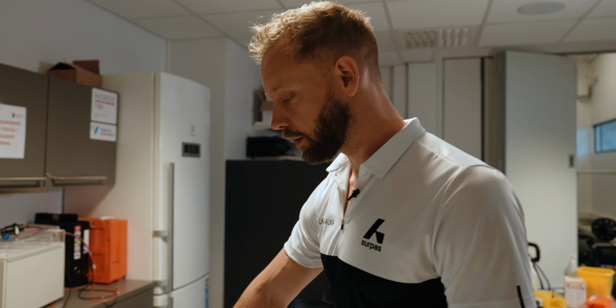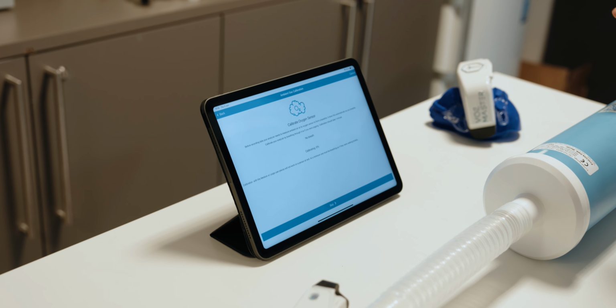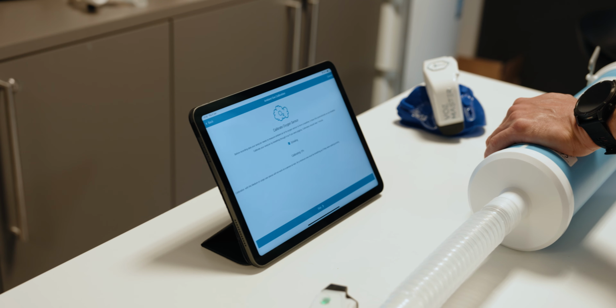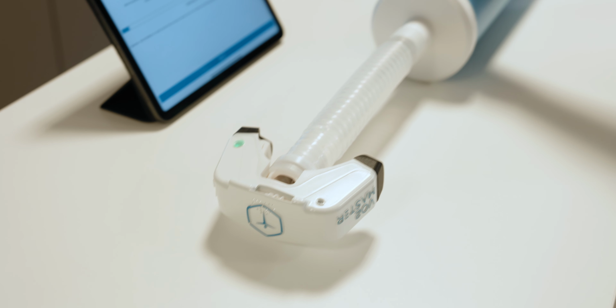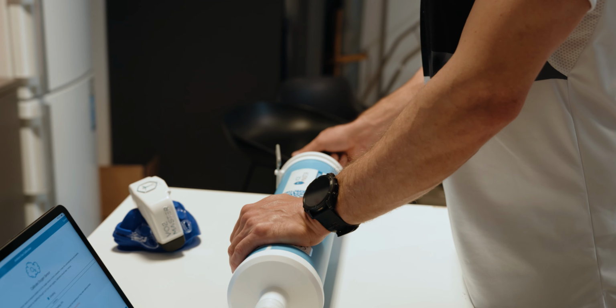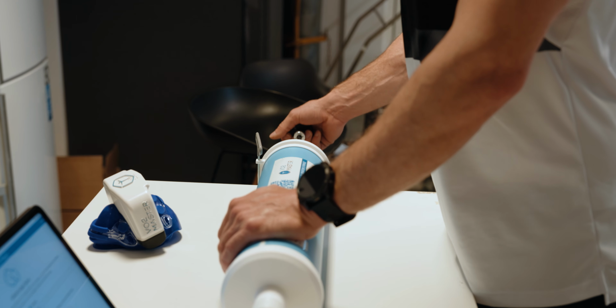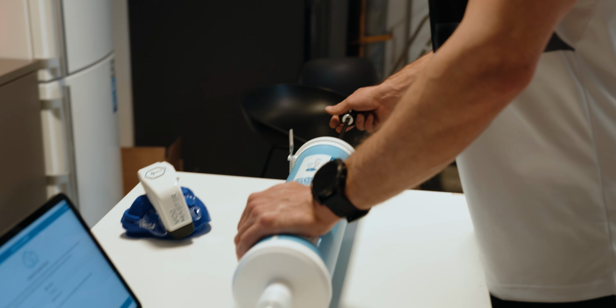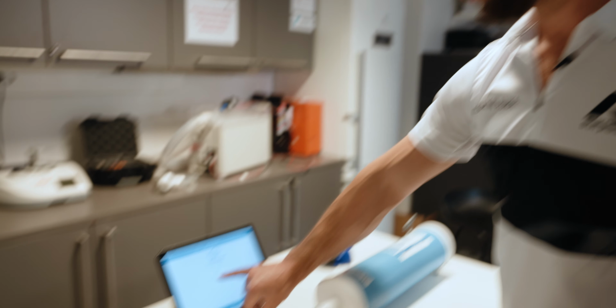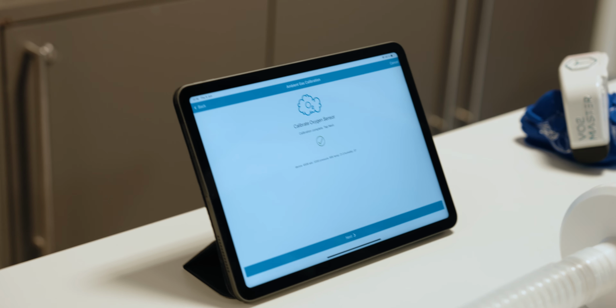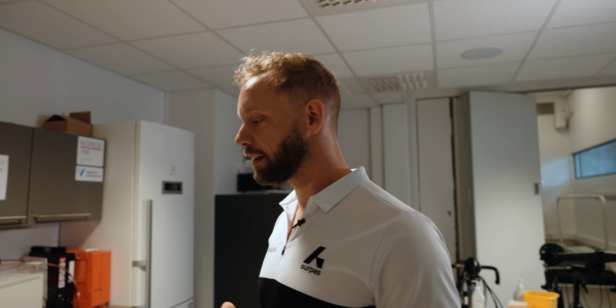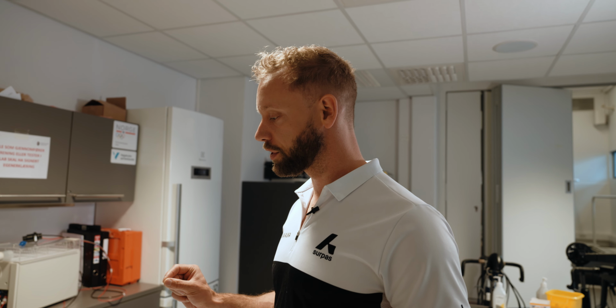The next part is now exactly the same, except you don't have to follow the metronome. You simply pump at a normal breathing pattern, and now you calibrate for the oxygen sensor or gas calibration. You will now calibrate for the amount of oxygen in the air. You will also calibrate for humidity, temperature, and pressure. Notice the ADC value. This is usually above a couple of thousand, between 3,000 to 4,000. And if you see this value drop significantly during calibration, as opposed to what it's usually at, that's a sign that you should look to change the oxygen sensor, or it's about time for you to order a service kit, the annual service kit.